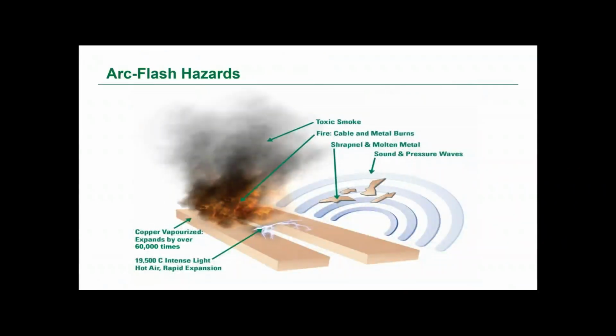To transition to arc flash, there are certainly plenty of hazards to talk about. It's really like a bolt of lightning, an intense light, sound, and energy all packed together. That high amount of heat, when it's discharged, can vaporize the copper bus bar, and that creates a huge amount of expansion in the conductors in the air. With that expansion in a fixed space inside the panel, it creates a pressure wave that can blow apart pieces of equipment, travel at over 700 miles per hour, and of course contain pieces of molten or burning metal and shrapnel. In addition, there's the risk of fire and toxic smoke that comes from the insulation and all the other materials inside the panel.